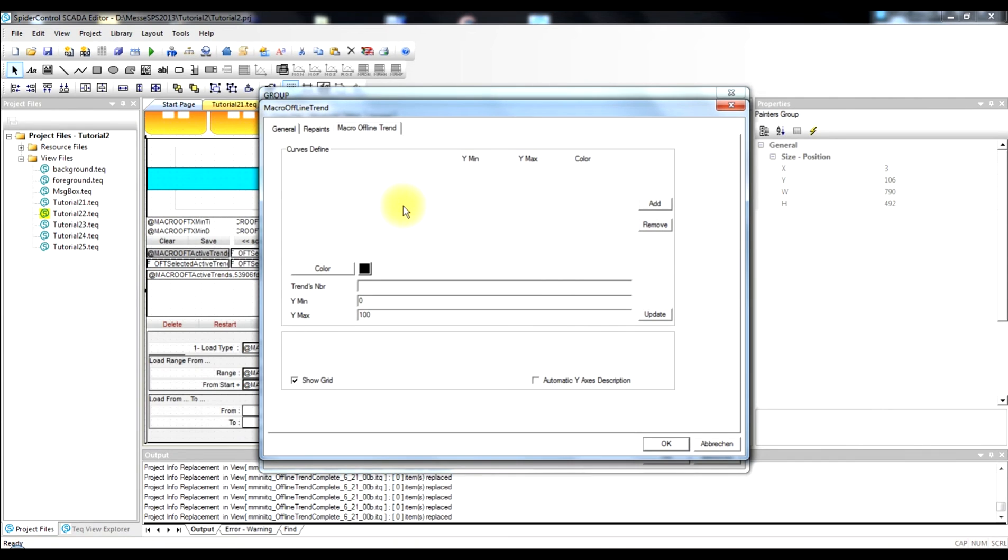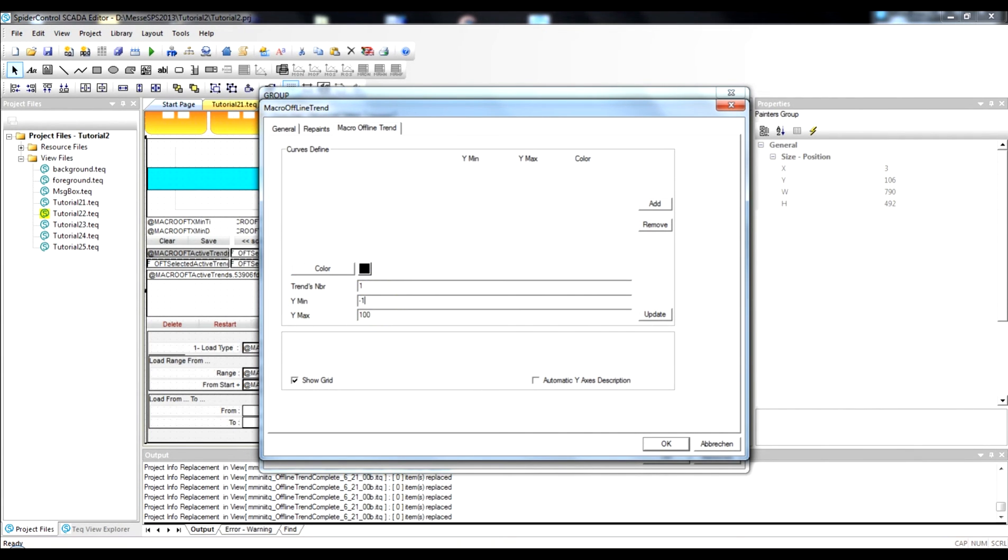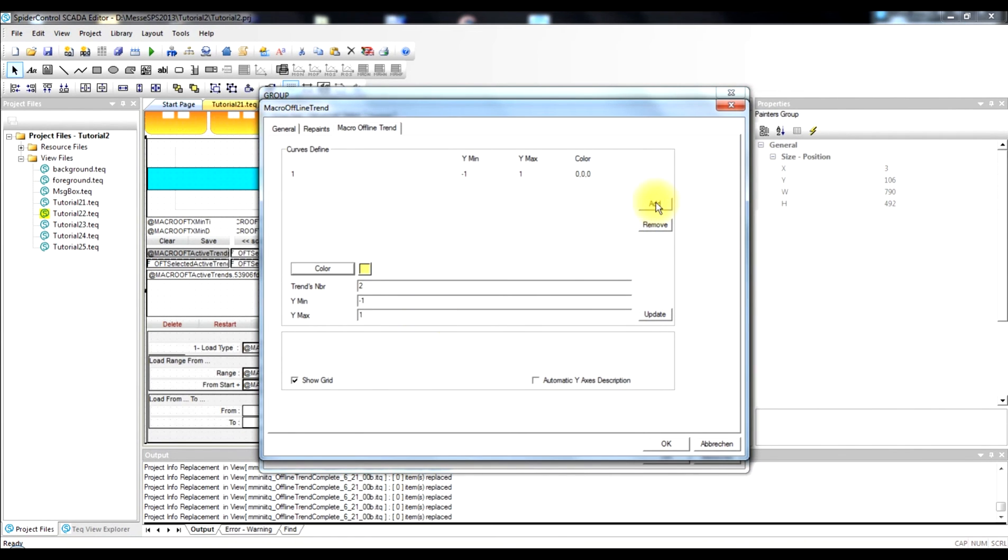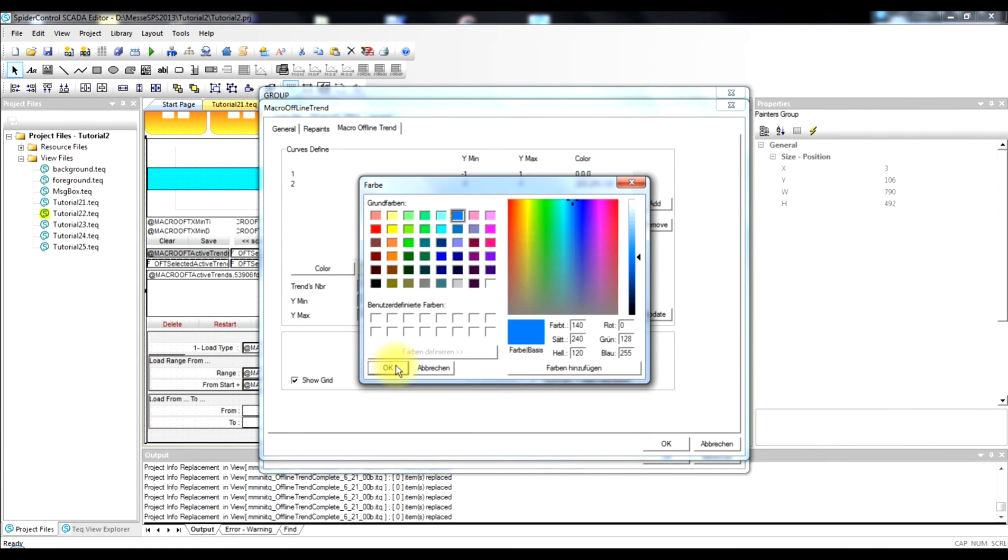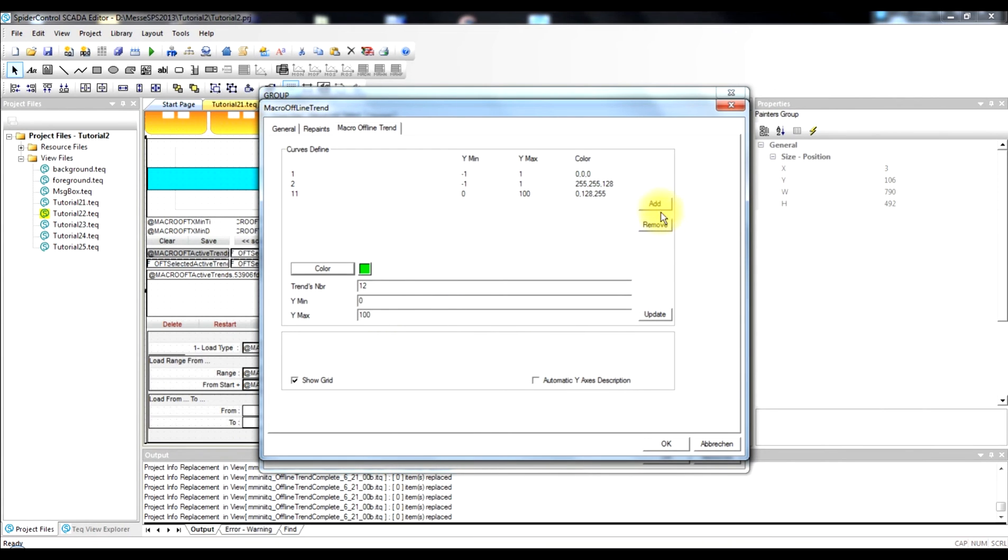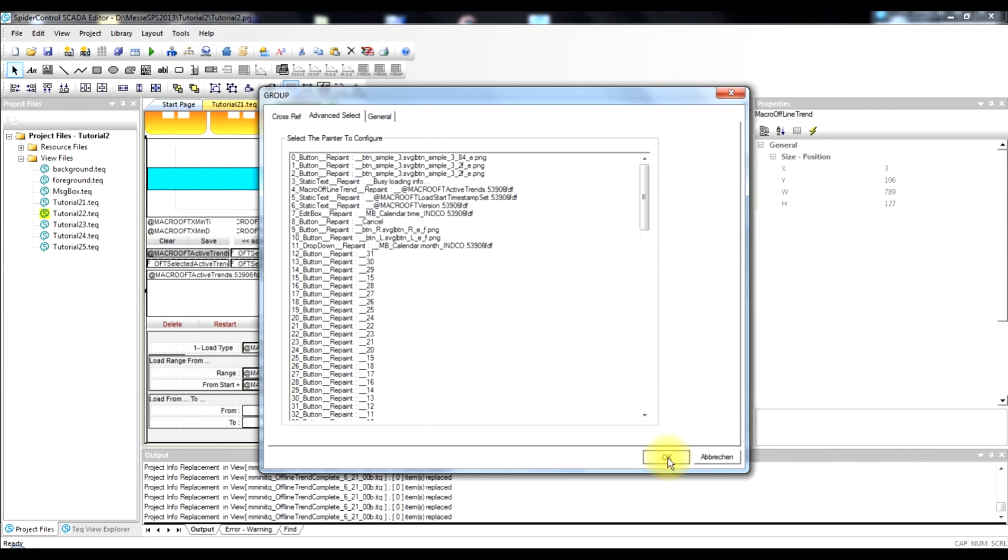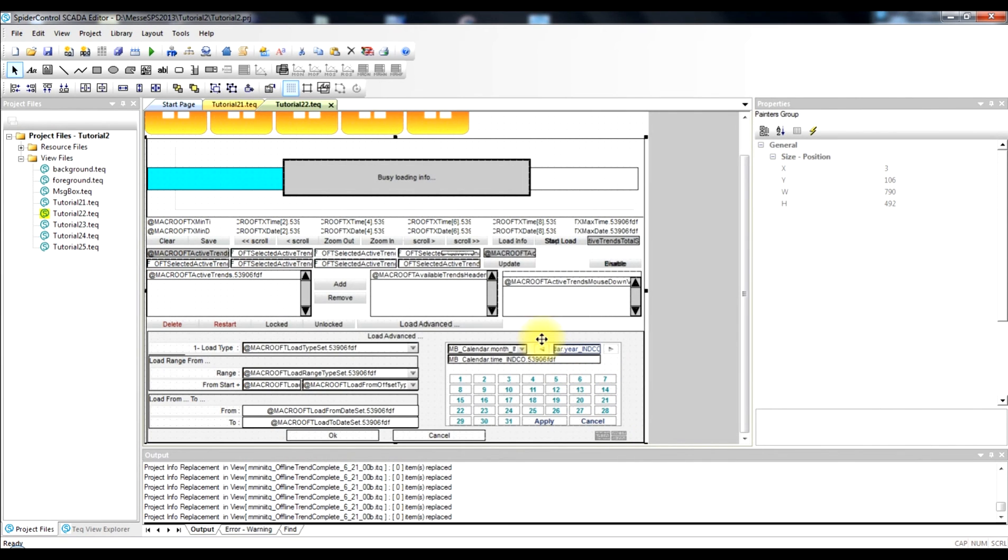So now in this object we can add the trend log numbers that we have previously defined or automatically imported by our harvesting. So we begin with the trend track number one. We choose the minimum and maximum. So this one goes between minus one and one. And we choose a color for that. And add it to the object. We do the same for trend number two. And so for the trends from the Phoenix PLC, which is the trend number eleven and twelve. We put a color to that. And choose the respective minimum and maximum area. We also choose for the automatic y-axis description. So this will show a y-axis description for each trend track individually. So this is the configuration.